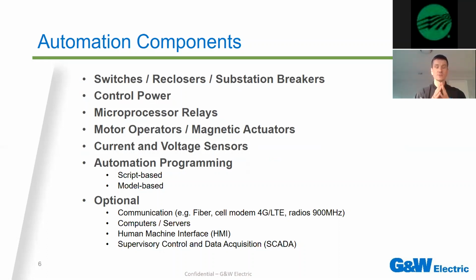Second component is control power, needed to power the microprocessor relay you see there. The next point is motor operators or magnetic actuators, which essentially replace the human muscle power required to open and close switches manually. Having a motor operator together with a relay that sends a command to open and close a switch is required for automation.